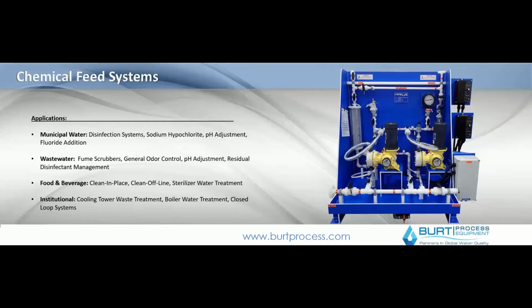What that use is, the chemical, really helps dictate the pump selection and then ultimately the system selection. As you notice as we go through, we've seen a peristaltic pump, motor-driven metering pumps, air-operated diaphragm pumps, gear pumps, progressive cavity pumps, and rotary lobe pumps. There are all kinds of different pumping technologies that can be utilized based on flow rates, pressures, whether there are degassing requirements, and chemical compatibility, which also plays into things like this.